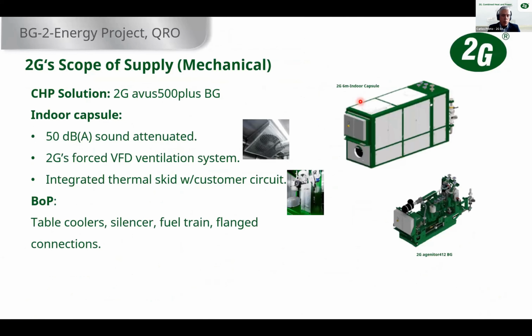Going specifically through every step in our scope of supply: we set up the 2G avus500plus running with biogas in this indoor capsule, with the 50 dBA sound attenuation I showed you. We supply the forced variable frequency ventilation system for the entire solution, giving the air needed internally at the indoor capsule for the right temperature, and also the air for combustion.